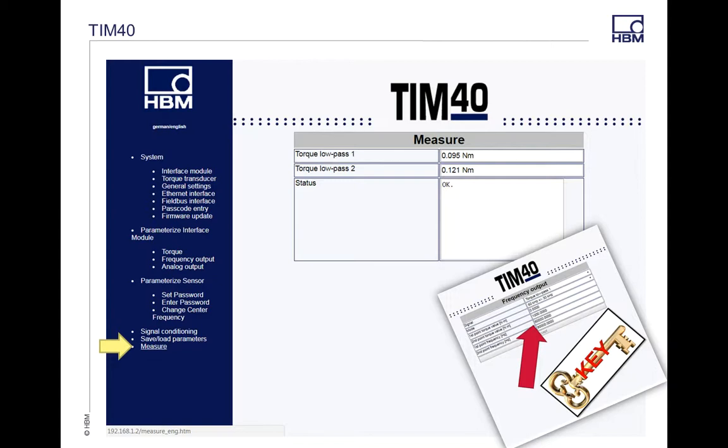This is a live screen but is not time-stamped in any way. What I mean by that is this is just a digital reading of your actual torque transducer — this is not a measurement mode. We've had some people try to use this as measurement, but it's not the same as your normal torque transducer measurement setup. This is setup only.